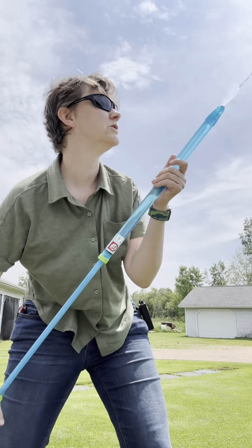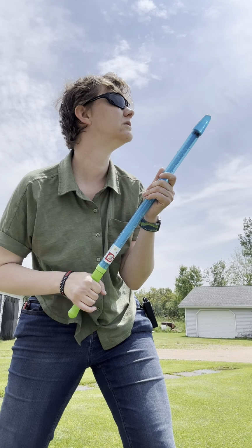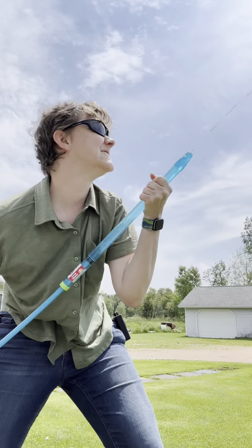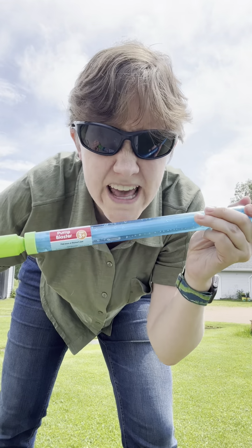So with pretty gentle pressure, 1, 2, 3, 4. I can empty it in 4 seconds. Let's see what it takes to get down to 2. 1, 2. To empty this in half the time means I doubled my Q, but it took way more than double the pressure to get it done. So as my Q increases, my friction loss way increases.